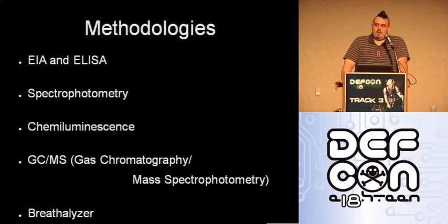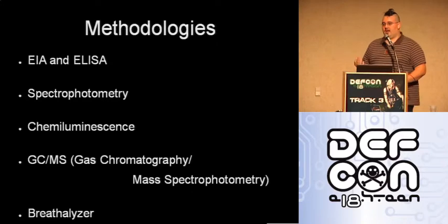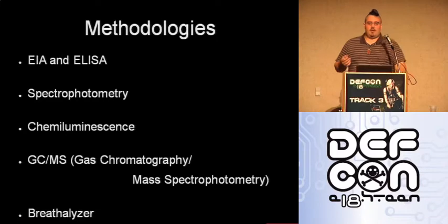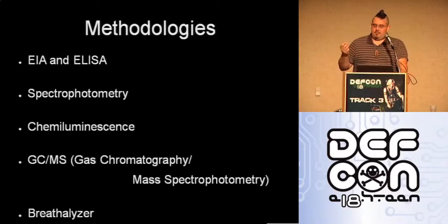Now, the way spectrophotometry works, where I work, we use what's called a dry slide. It's a newer kind of spectrophotometry. It's just now starting to become more common. What happens is the machine will dispense, say, 5 microliters of specimen onto the slide, and the slide has filters in there to filter out what it doesn't want. And then what isn't filtered out goes down to the bottom, which has enzymes.